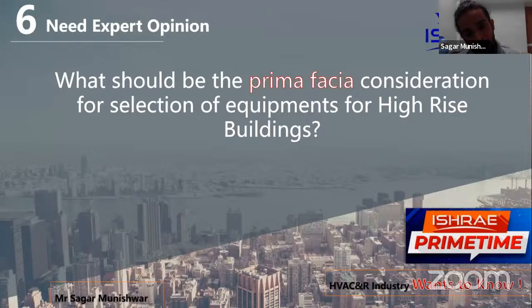Again, in a high rise, having reverse return piping is a cost, because you'll have to have extra piping running till the top and the piping coming back. So instead, you can have a pressure independent balancing control valve across each AHU or each fan coil unit, which can take care of the required pressure drop across all the system. I would also like to touch upon a few aspects, like one of the panelists did mention about the staircase pressurization system. When you select the fans for a staircase pressurization system for a high-rise building, we see to it that it is divided amongst equal floors. I mean to say, if it's a 40 or 50-storied building, it's not wise to have only one fan located on the top and pressurizing the system.